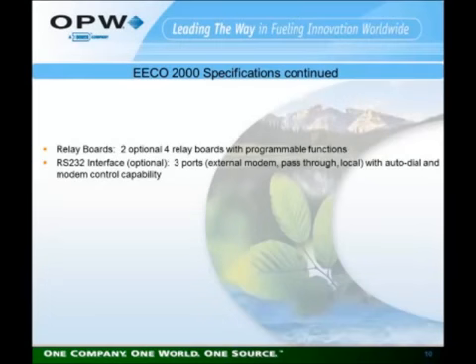The EECO 2000 also has RS-232 interface capability. With the RS-232 expansion board, there are 3 ports: 1 port for an external modem, 1 port as a pass-through port that you can connect to the EECO 2000 from externally and pass through to another device, and a local RS-232 port. When equipped with an external modem, it can be programmed to auto dial out on specific alarms or troubles and notify another device externally.